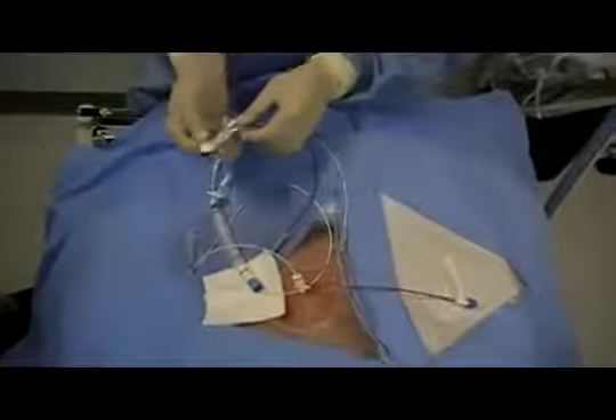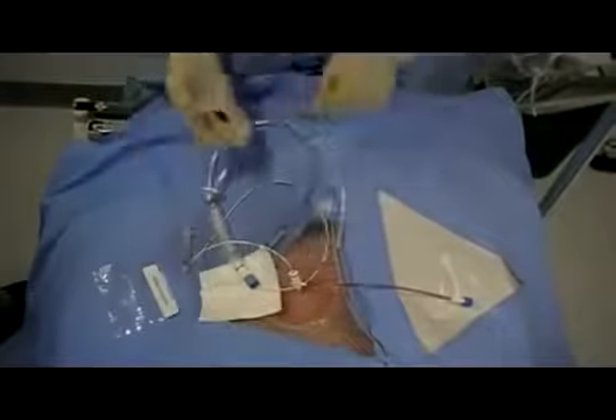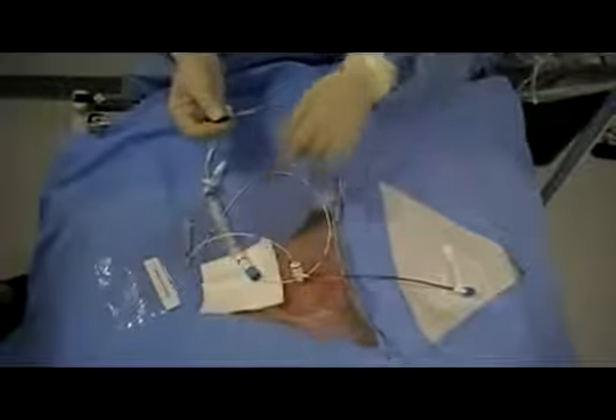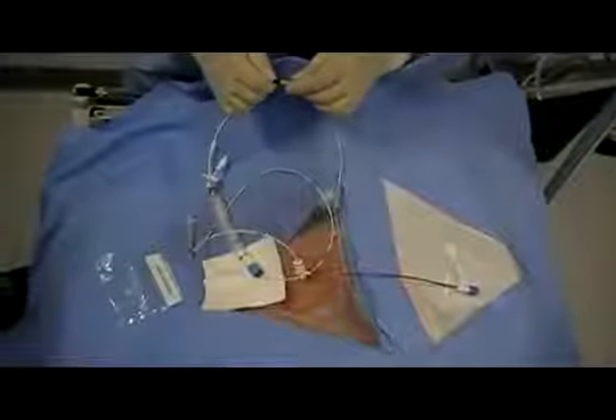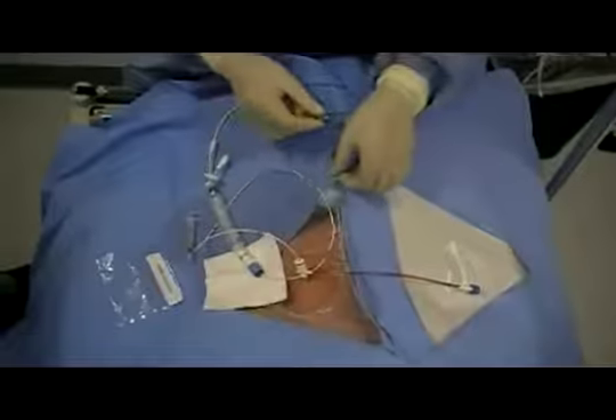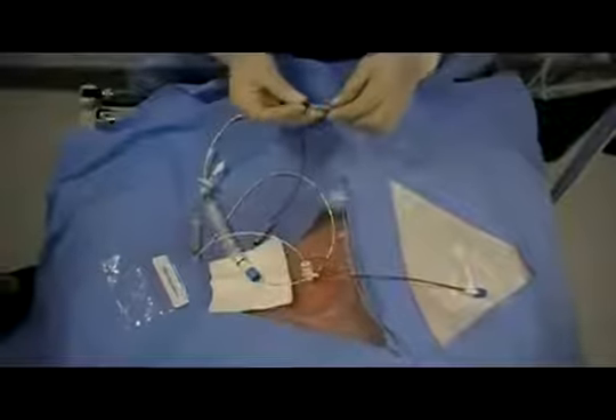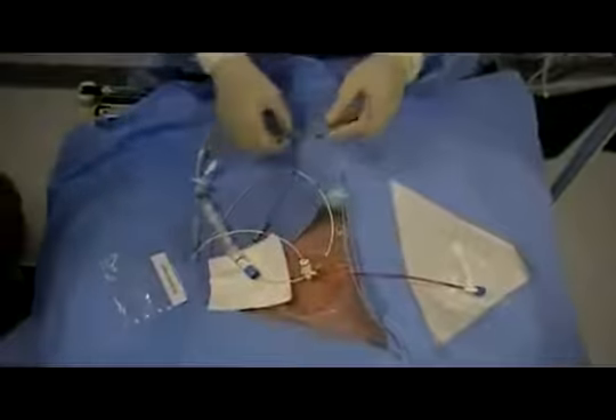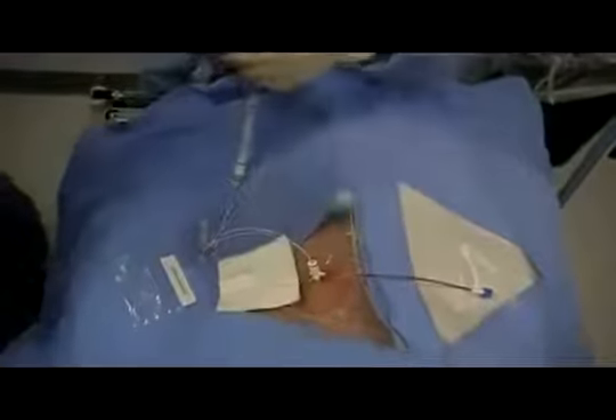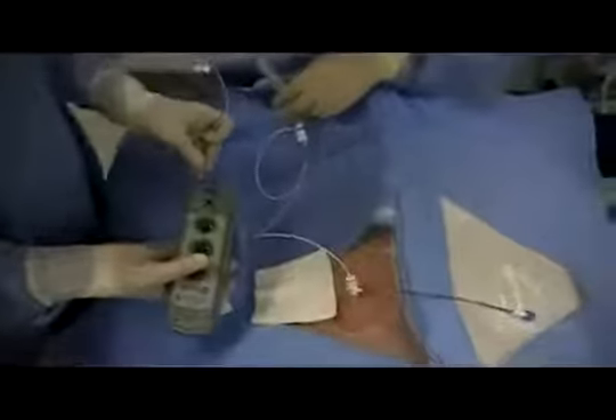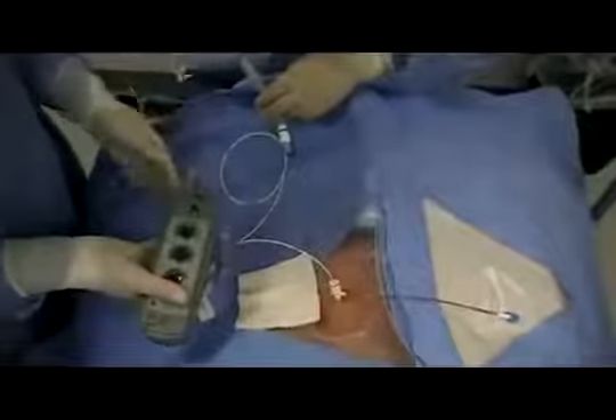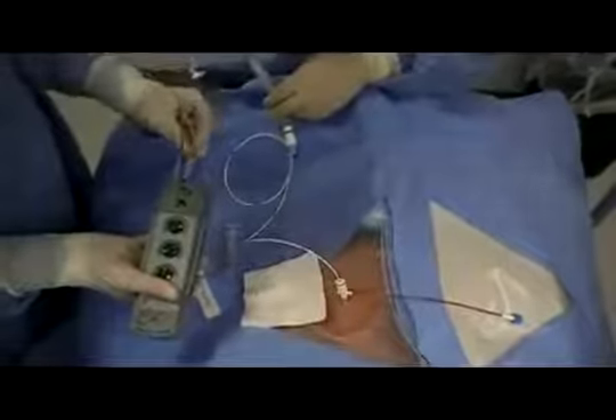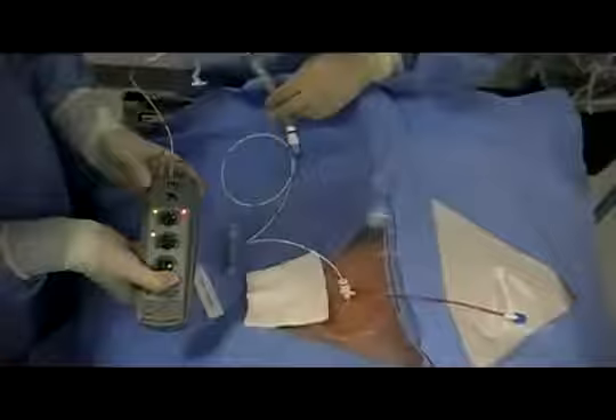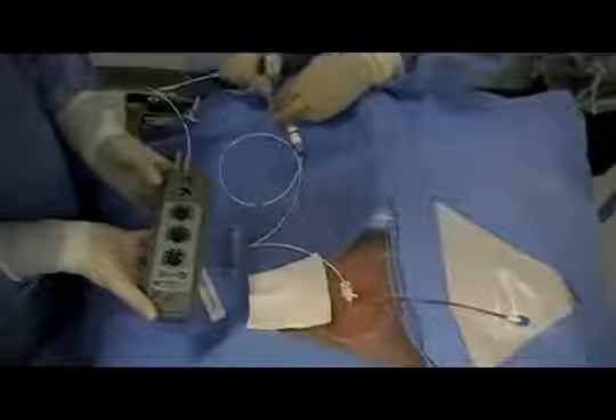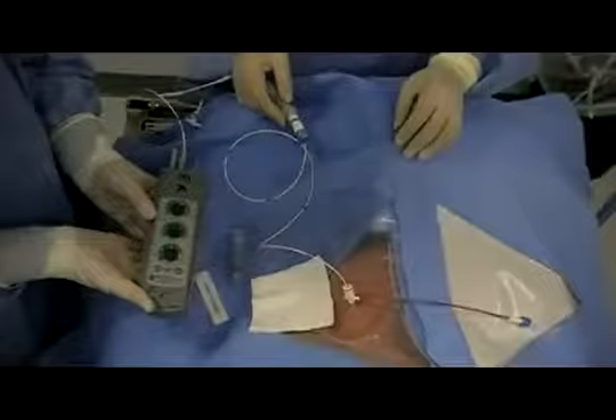Once the balloon is inflated, the sterile operator should open the package with the adapters that connect to the distal end of the pacing wire. Once the adapters are inserted, the distal end of the catheter can be handed off to a non-sterile operator. Ports should be inserted positive to positive and negative to negative. At this time, the pacing box can be turned on. The rate should be at least as high or higher than the patient's innate rate.